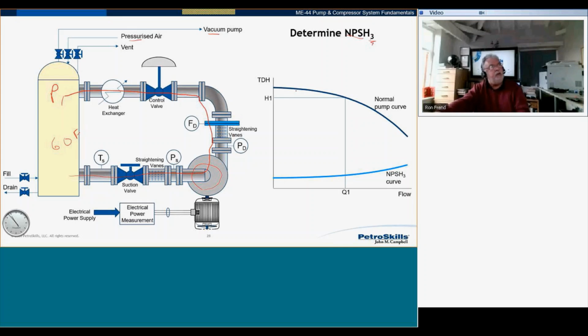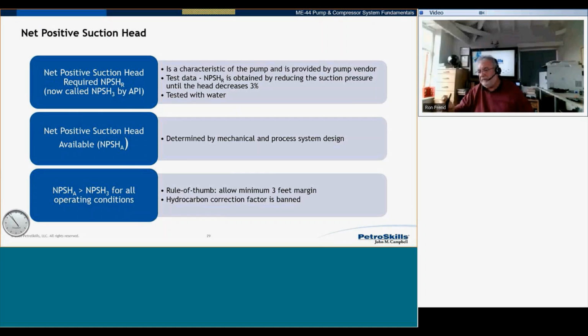And what we do is we check the pump curve. Then what we do is we start to shut in the suction valve, or we reduce the pressure over here until we start to get the onset of cavitation, bubbles start to form, and we lose efficiency. And the pump curve shifts down to here. And once we've got a 3% drop in head, that is classed as the onset of cavitation. And that defines your NPSH for the vendor. So keep that in mind. And just remember that at that value of NPSH, you're already cavitating.